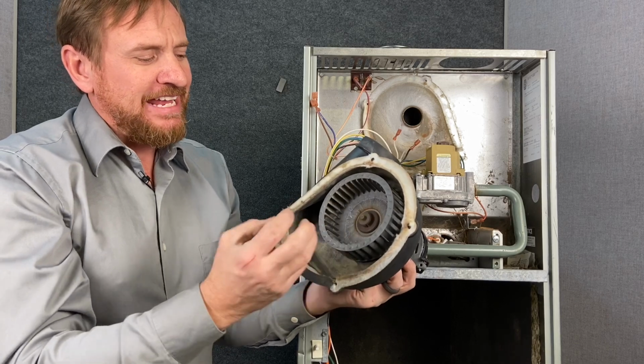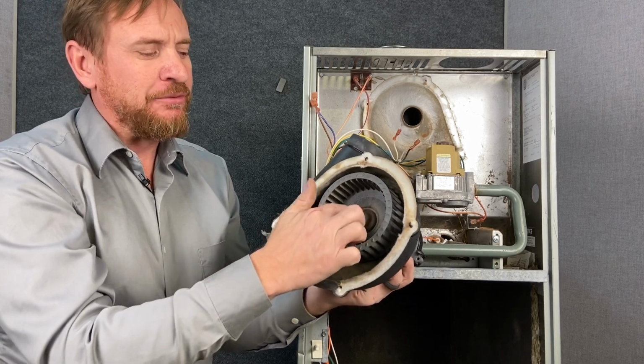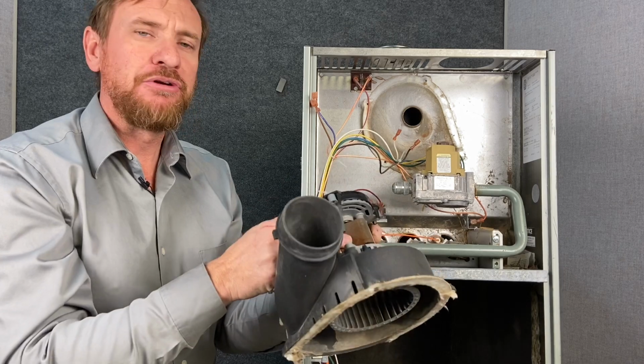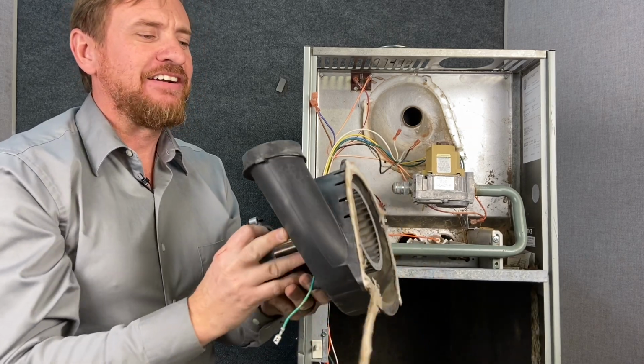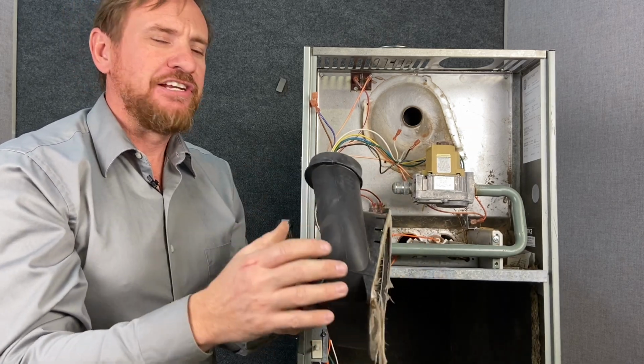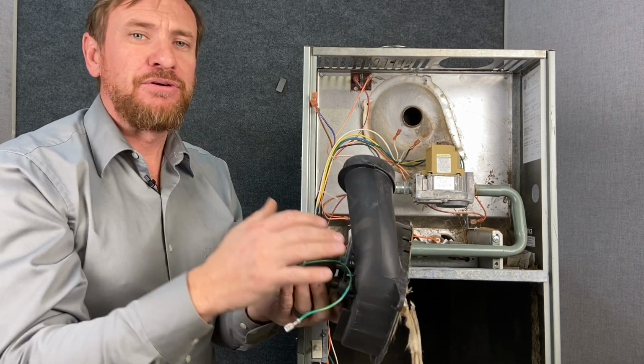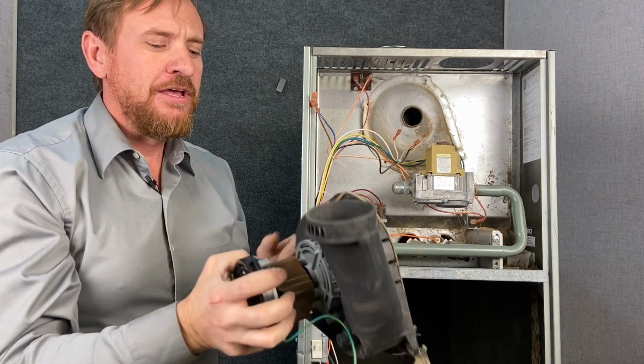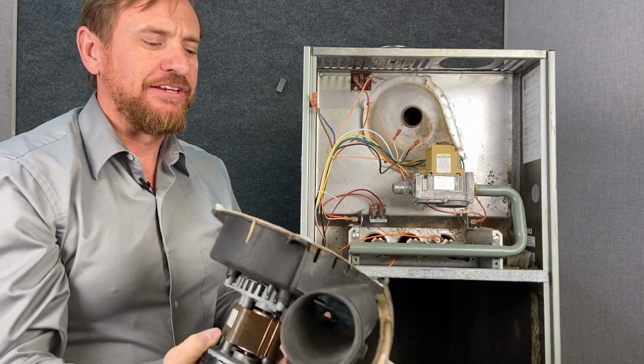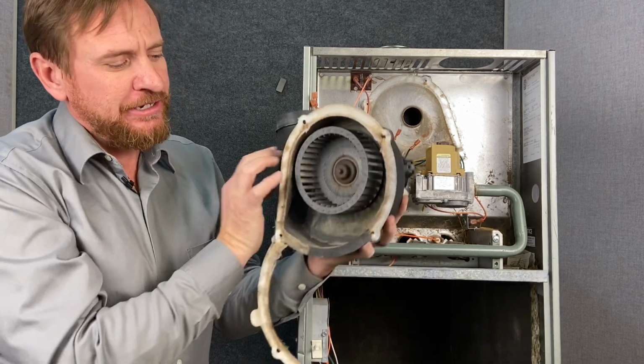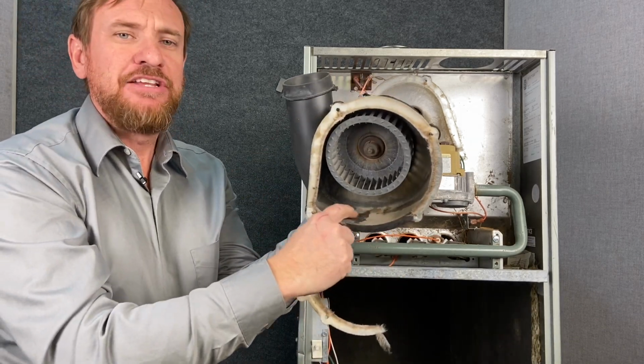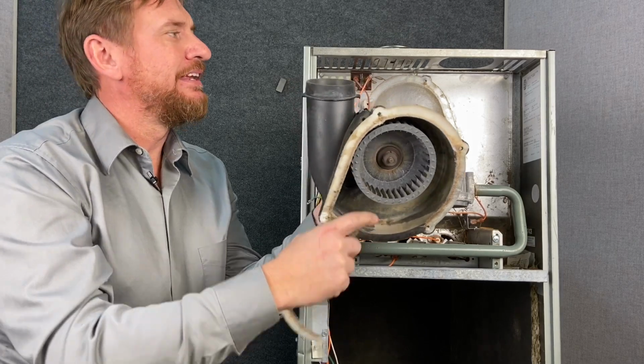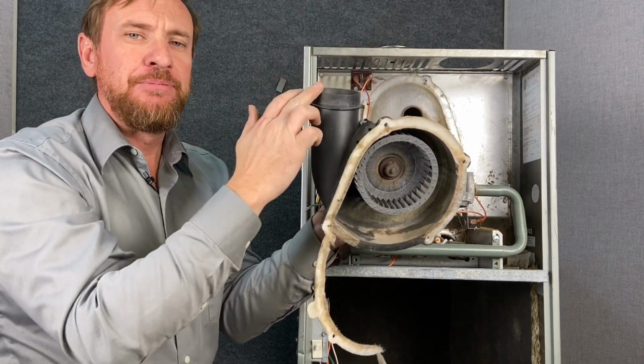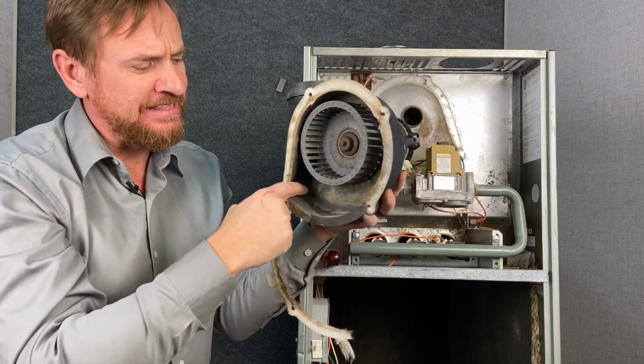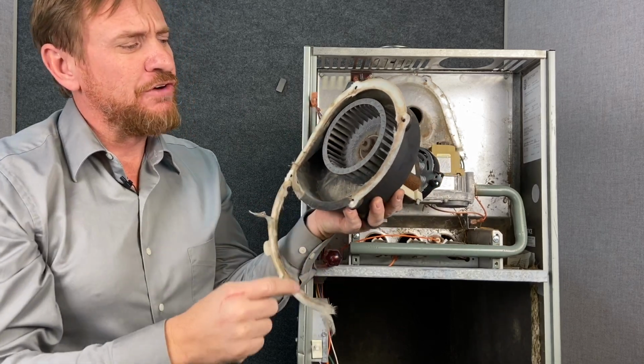Now because of all that heat running through here, it's almost impossible to change just this wheel. So when this motor goes bad, you change this entire housing. It's inducer draft housing, inducer fan housing, combustion blower. All these are words used for this, but it's this whole entire housing that we replace. What I want to point out on this particular model is we have some stains right here. And most likely what that is there was water coming down to the flue pipe from the cap or something like that was probably causing these stains over time.